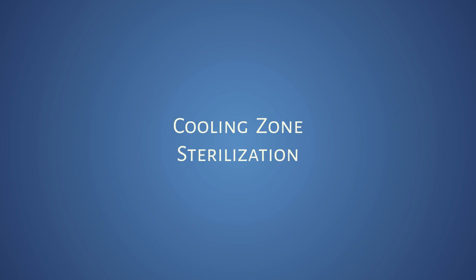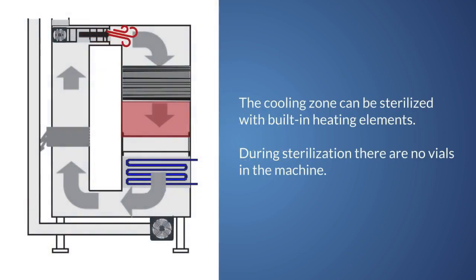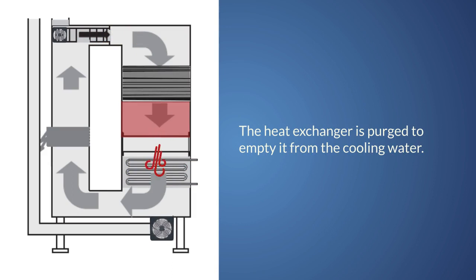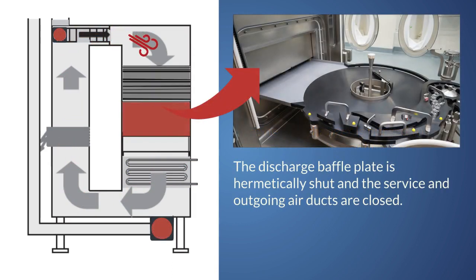Now let's take a look at how the cooling zone is sterilized. The cooling zone can be sterilized with built-in heating elements. During sterilization, there are no vials in the machine. The heat exchanger is purged to empty it of the cooling water. The discharge baffle plate is hermetically shut and the service and outgoing air ducts are closed.